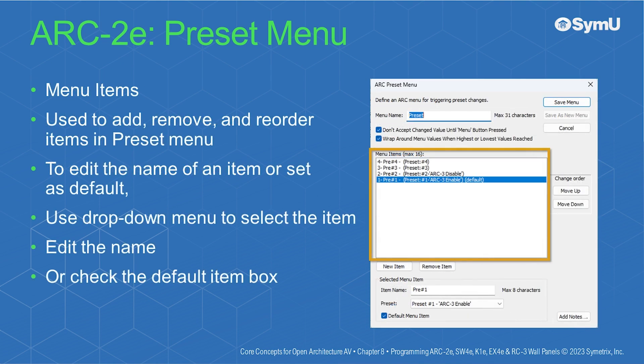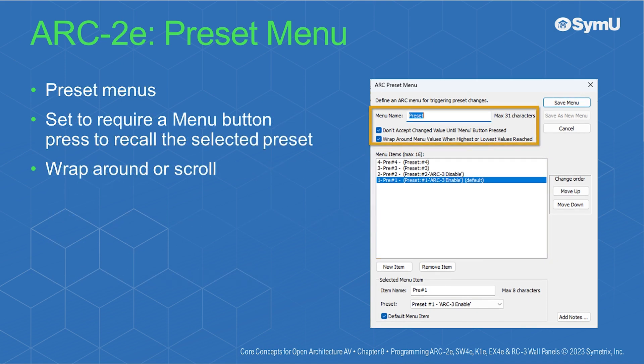A preset menu can be added from the Edit Arc2E window by selecting Add Preset Menu. The menu items portion of this window is used to add, remove, and reorder the items of the preset menu. To edit the name of an item or set an item as the default, use the drop-down menu to select the item, then edit the name or check the box to make it the default item. Preset menus can also be set to require a menu button press to recall the selected preset, and the menu can be programmed to wrap around or scroll between available items.